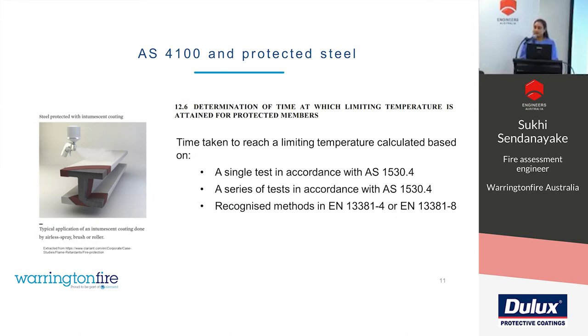So now we can talk about protected members. Clause 12.6 of AS4100 gives us guidance on how to determine the fire resistant performance of protected members. And AS4100 states that the time taken to reach a limiting temperature can be calculated based on either a single test or a series of tests, and all of them have to be conducted in accordance with AS 1530 Part 4.